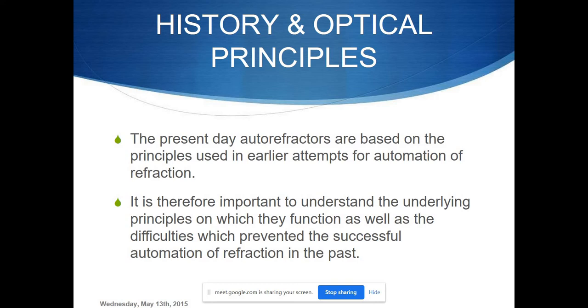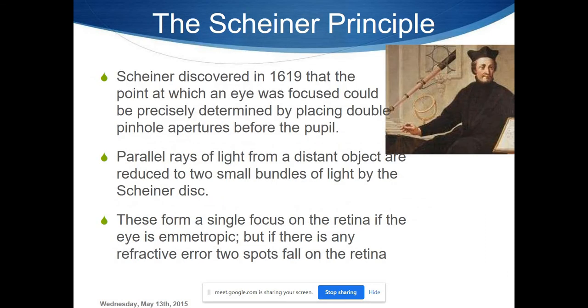Most autorefractometers in use now are based on principles used in the early instruments. We'll go through one by one how these autorefractometers were developed and how the principles and optics behind them evolved. It was Scheiner who actually came up with the foundational principle, using a dual or double pinhole approach.